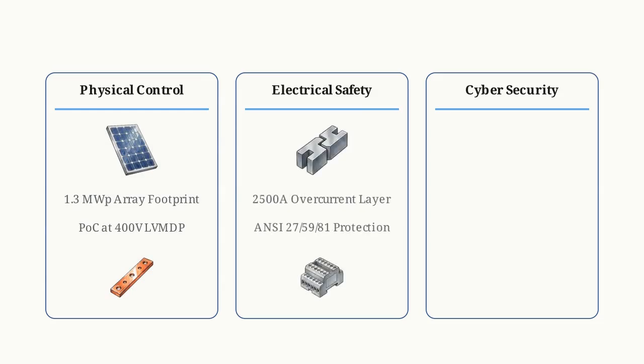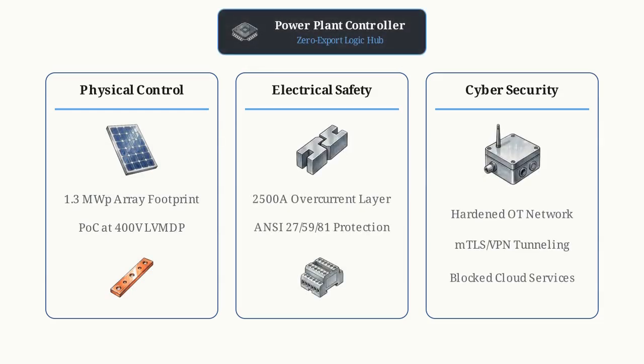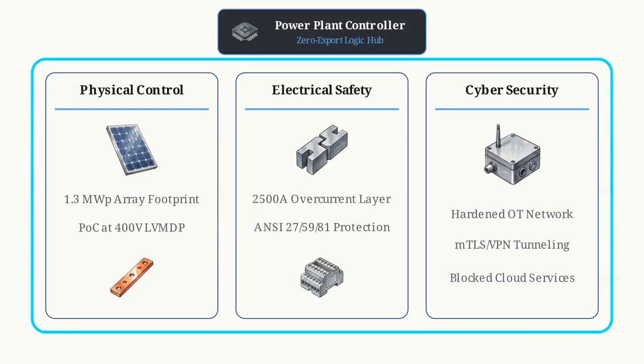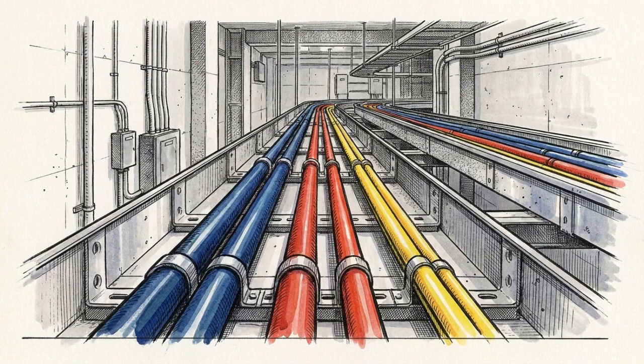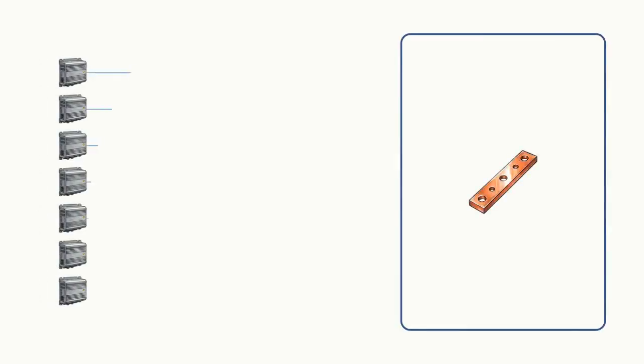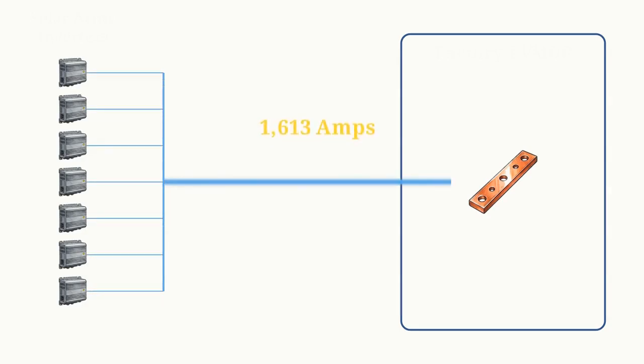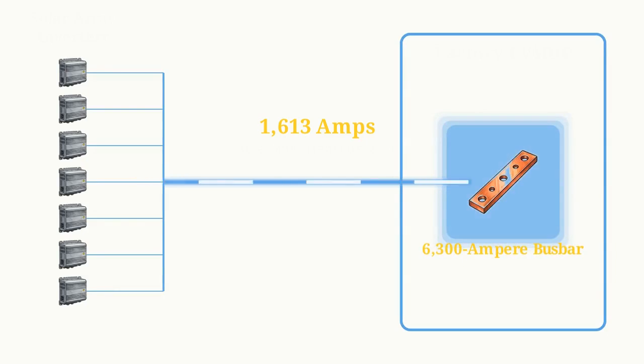Designing a megawatt array is an exercise in strict boundary management. Physical, electrical, and cyber limits must be locked down to guarantee the host facility remains protected. Stepping back from the point of connection reveals the raw electrical reality of the AC interface. At maximum output, the array generates a combined plant current of 1,613 amps, which routes directly toward the factory's 6,300 ampere bus bars. This diagram illustrates the primary mechanical gateway built to manage that load.